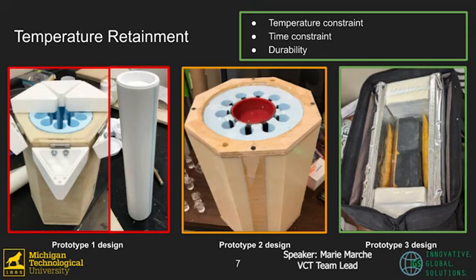Prototype 3 experienced a design makeover where vacuum insulated panels were used, which have an R value of R25. Additionally, the PCM changed location to the outside of the vial sleeves. These design changes have allowed Prototype 3 to meet our constraints.